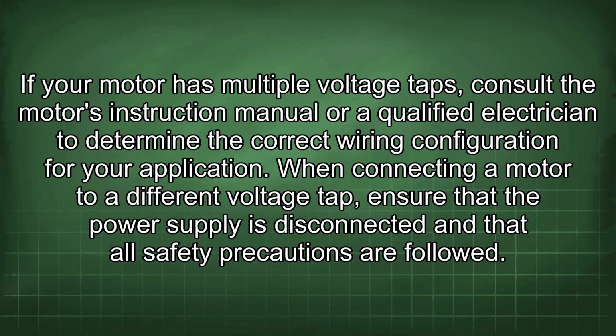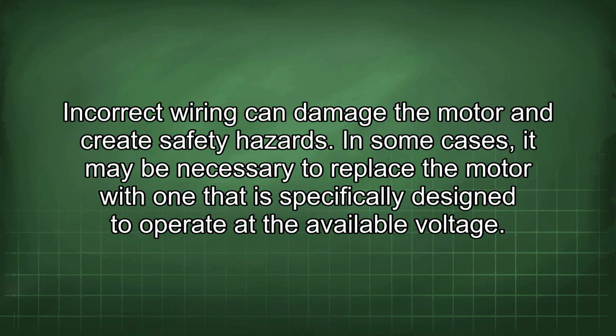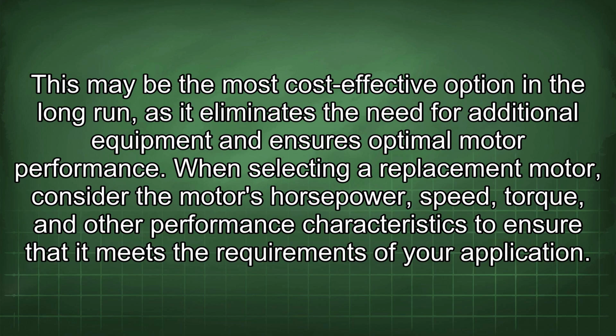When connecting a motor to a different voltage tap, ensure that the power supply is disconnected and that all safety precautions are followed. Incorrect wiring can damage the motor and create safety hazards. In some cases, it may be necessary to replace the motor with one that is specifically designed to operate at the available voltage. This may be the most cost-effective option in the long run, as it eliminates the need for additional equipment and ensures optimal motor performance.